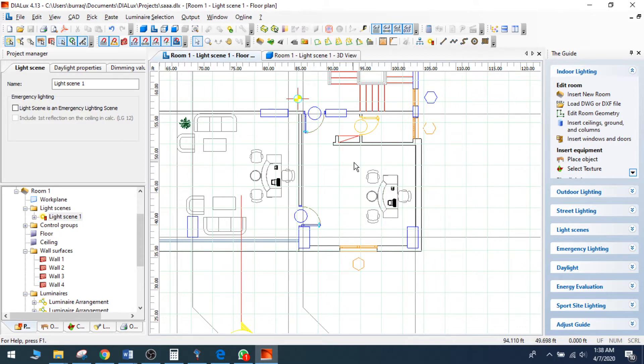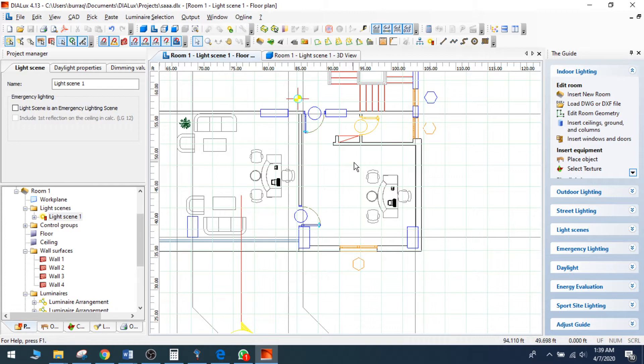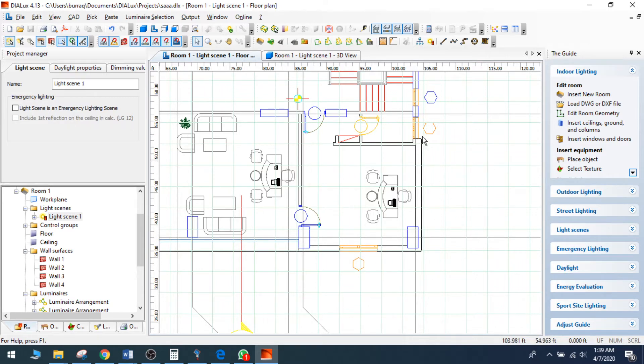25% of the total lux. It means if you have a requirement of 100 lux in a total system, then in emergency system we only need 25 lux. So 25 percent lux level is required for emergency lighting design.